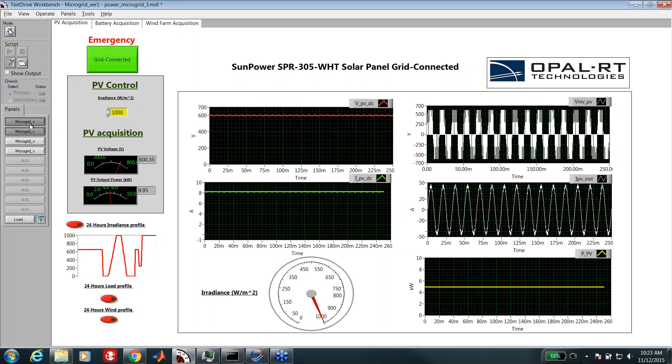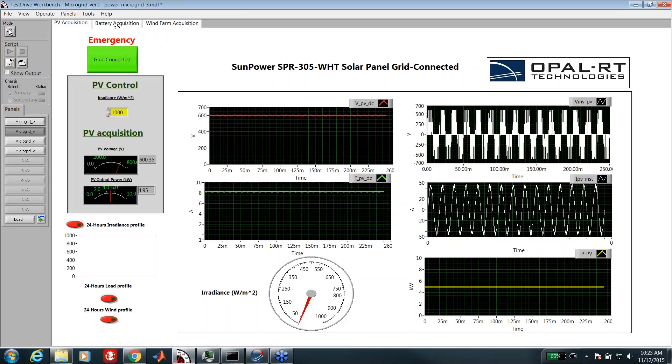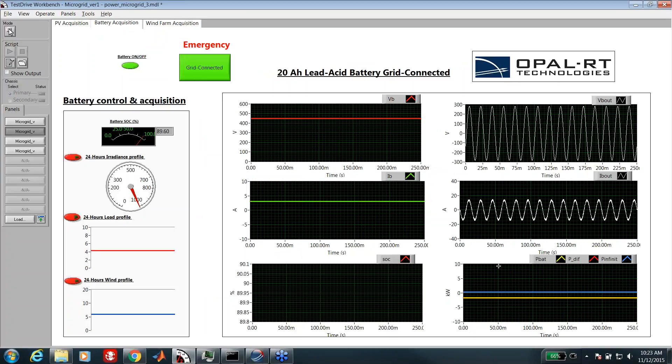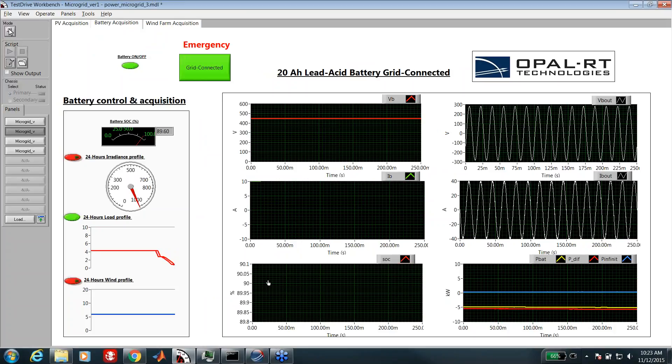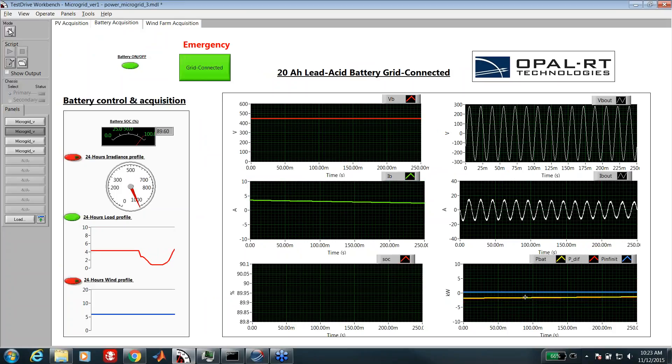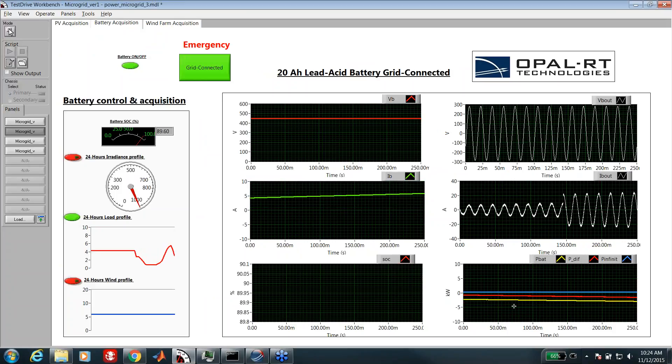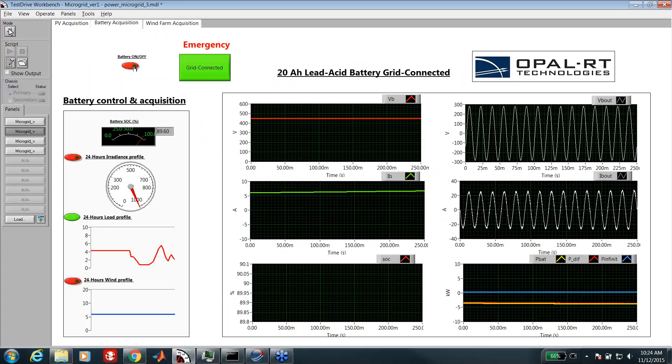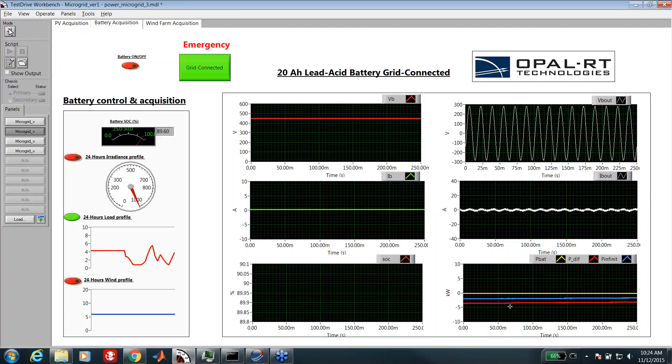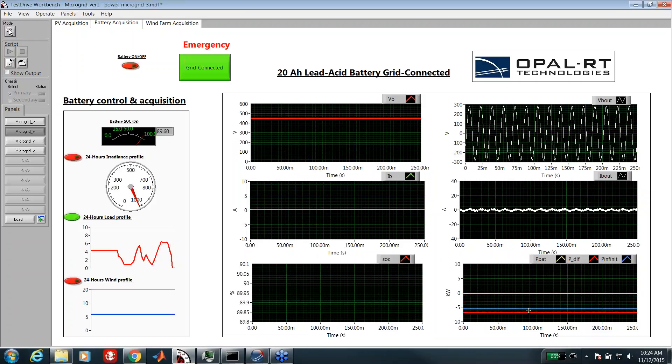Here we have another tab that will give the results from the battery and the behavior of the battery. We can also apply some 24 hours load profile. We can see that the control will ask the battery to always follow the power difference, as you can see here. If the battery is disconnected, it's the distributor that will deliver the difference of the power, as you can see here from this graph.